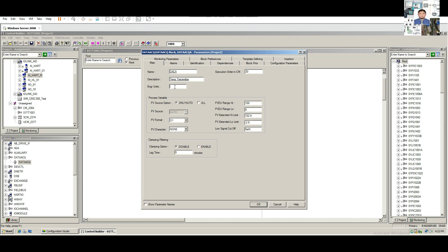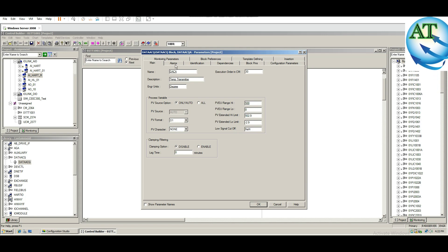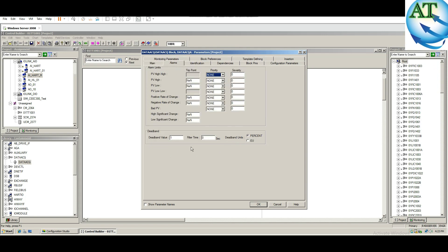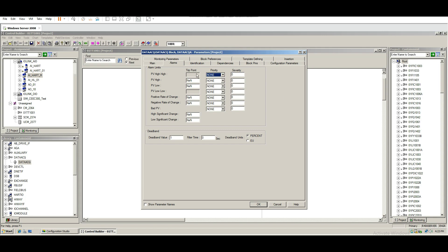Put the description 'Temperature Transmitter'. Then set the engineering unit to degree. PV source must be only Auto mode. In the PV high range, we set it to 0 to 500. In the PV extended high range, when it is 100 it shows 102.5 — set it to 500, which gives 500 plus 2.5, so 502.5. In the alarm section, you can put alarm values. Different types of alarm priority are showing: journal, low, high, urgent. Journal means no alarm, then low alarm, high alarm, urgent alarm — you can enable any of these. First you have to set the PV high range for the alarm to be active. Select urgent and put the high value as 450, with range up to 500.